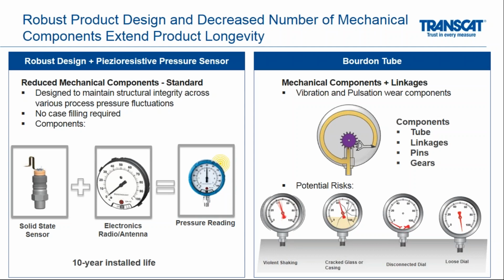And what ends up happening is you have this violent shaking that can't happen with the wireless pressure gauge. You have cracked glass. You have disconnected dials, and you have loose dials, all because those different parts could potentially get damaged. Again, with the wireless pressure gauge, with only one moving part, the solid-state sensor takes all of that aggressive application and then puts it out in a nice dial format that doesn't vibrate or can give you some more information if something goes wrong.